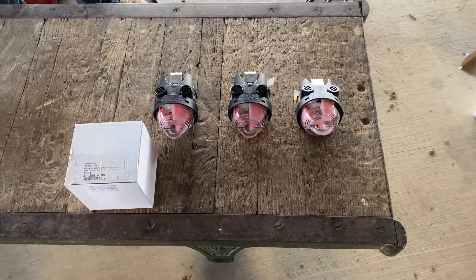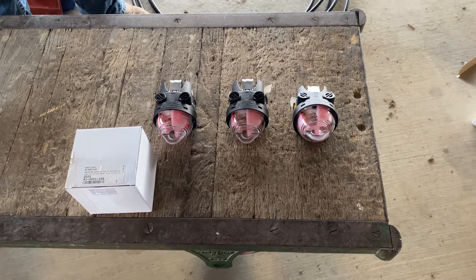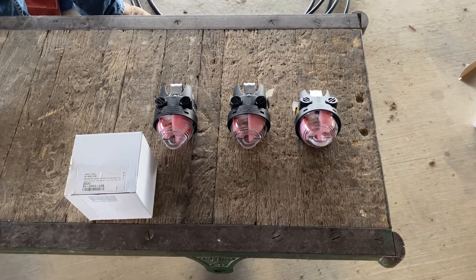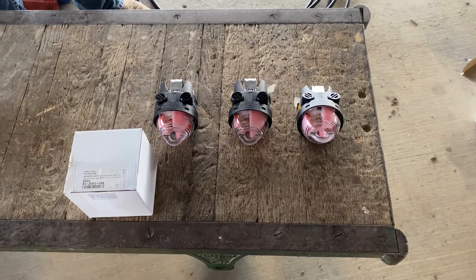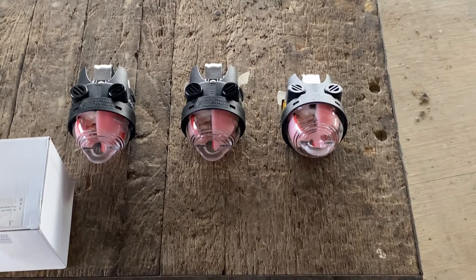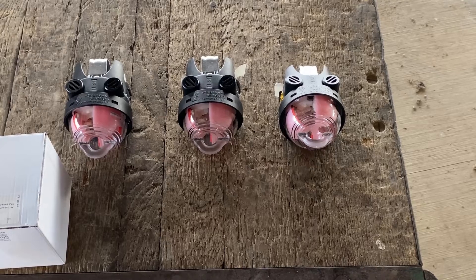This morning we're going to test three Power Delivery Partners faulted circuit indicators before we put them on the line. These are brand new out of the box. The number is 413001-108. We have the flag set for two days, 48 hours.